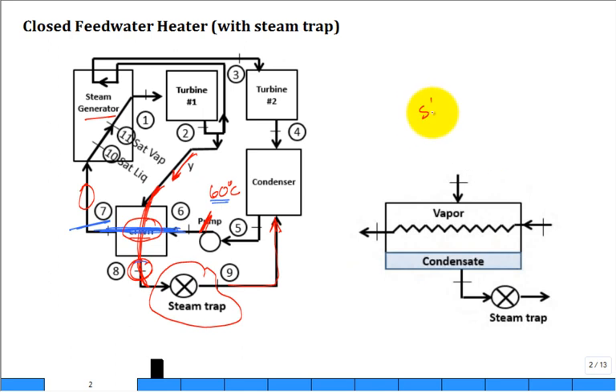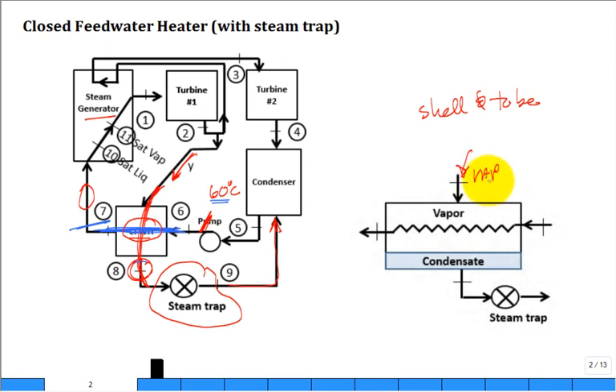The closed feed water heater is basically a shell-and-tube heat exchanger. On the shell side, steam comes in — it could be a two-phase high-quality mixture, saturated vapor, or slightly superheated vapor. On the shell side going out, you have condensate. What happens is: steam vapor contacts the colder tubes, condenses on them, drips off, and collects at the bottom. As it condenses on the tubes, it transfers heat into the colder fluid inside the tubes, heating it.